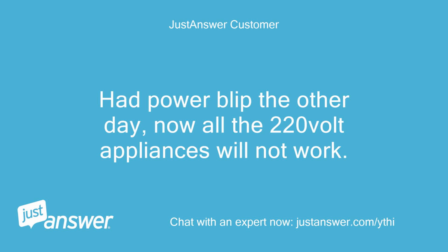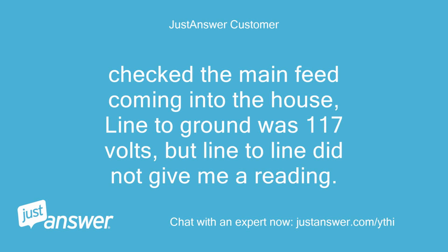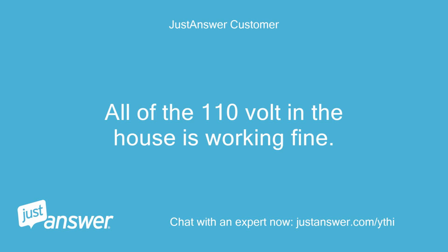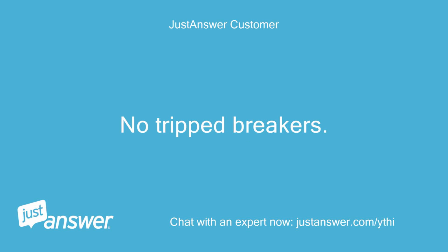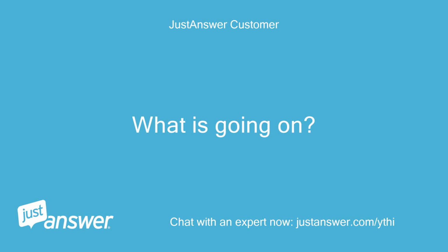Had a power blip the other day, now all the 220-volt appliances will not work. Check the main feed coming into the house. Line to ground was 117 volts, but line to line did not give me a reading. All of the 110 volt in the house is working fine. No tripped breakers. What is going on?